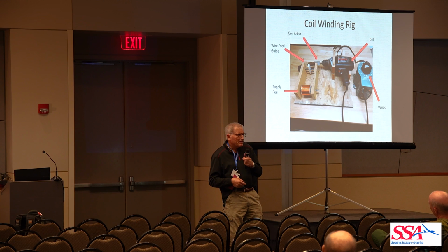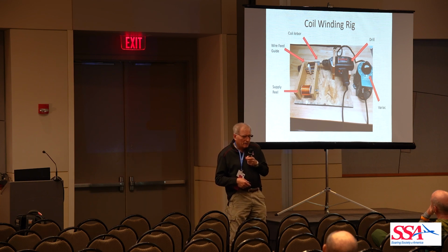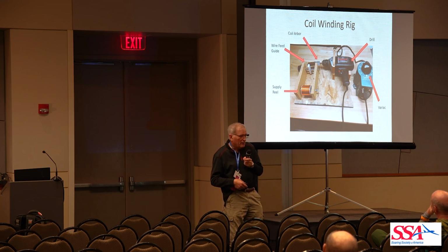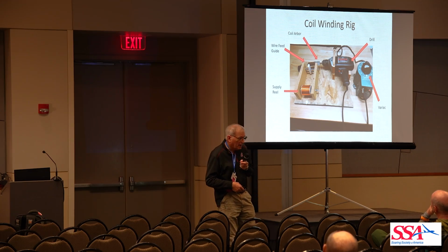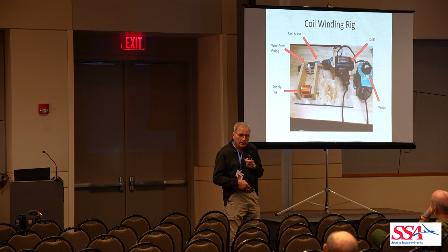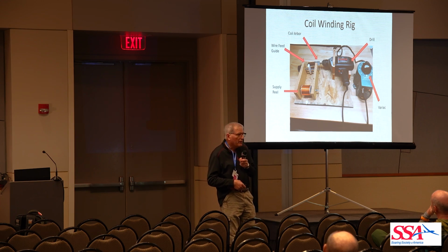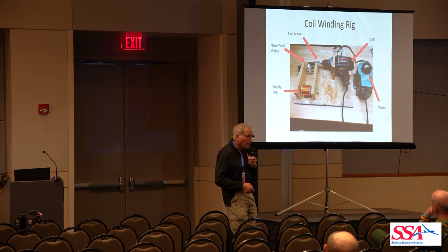One of the troubleshooting tips from DG is to check the resistance of the coil. I think they say it should be around 400 ohms with a new one, and if it gets down below 250 or 200 ohms, they say replace it. Well, you can't get them anymore, so you have to rewind them. I've rewound a number of them for myself and for other people.